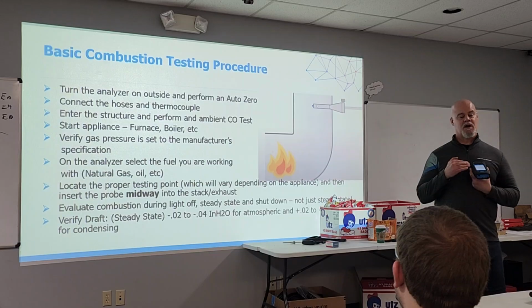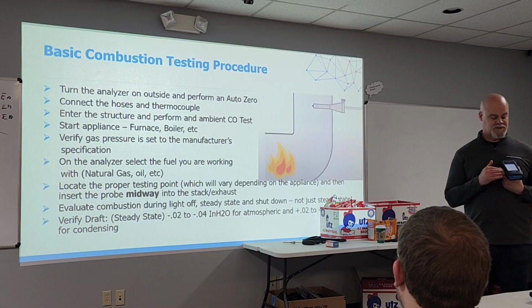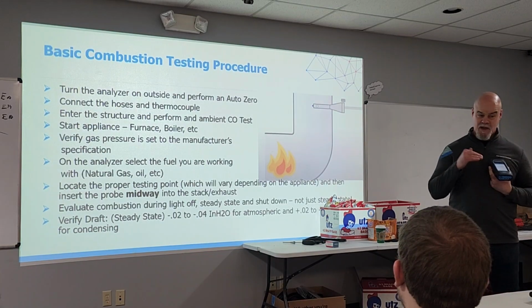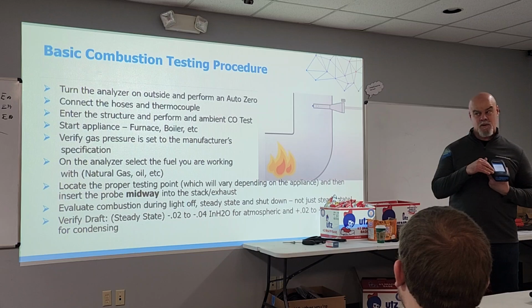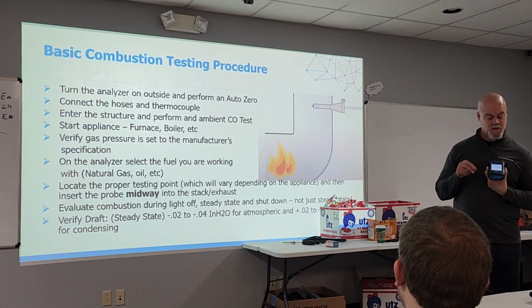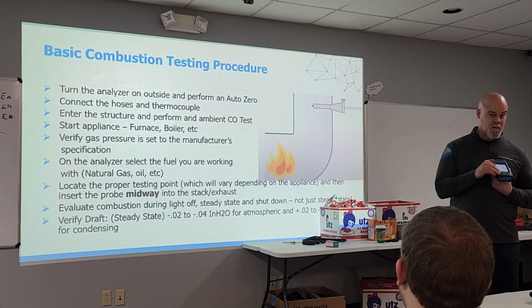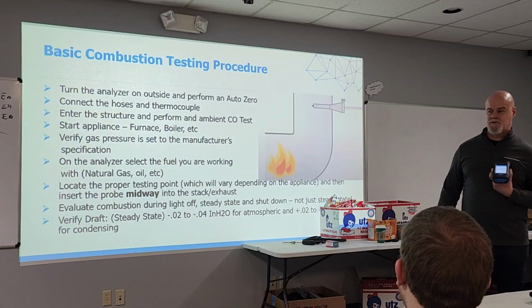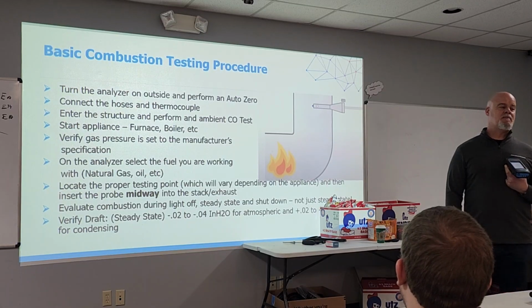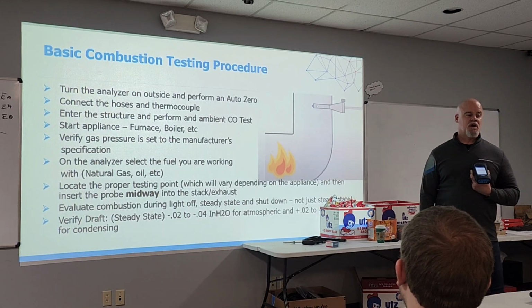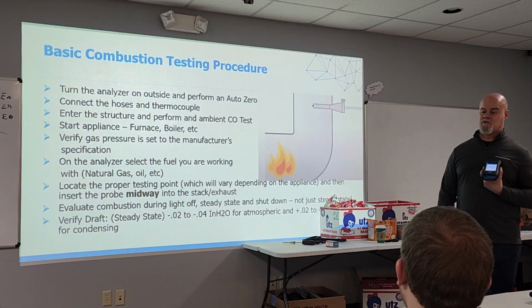So if you foul my startup protocol by starting it up indoors, and there was 100 ppm of CO in the room but your detectors hadn't gone off yet, it's going to show you 0. Then if you went to work on a furnace or boiler in a room with 200 ppm, it would only show you 100, because you've already negated the first 100.